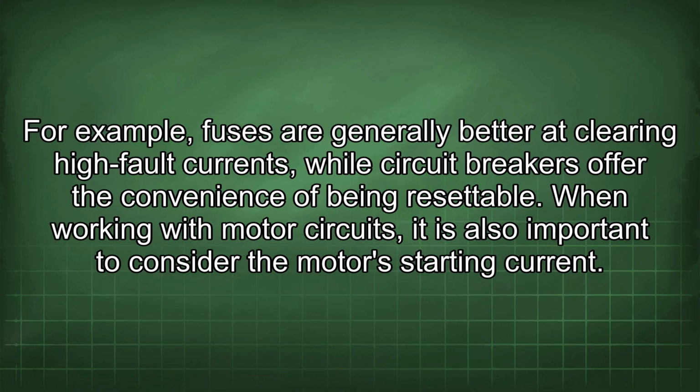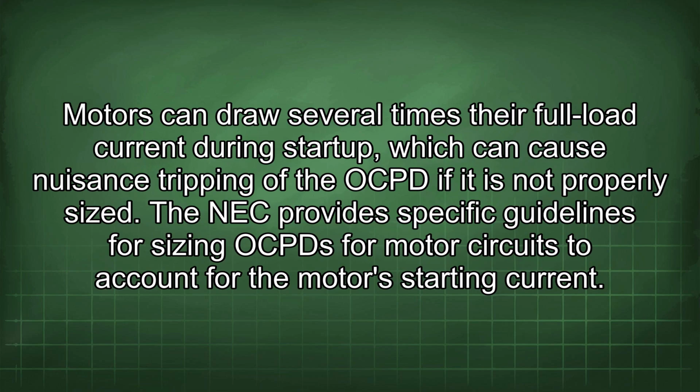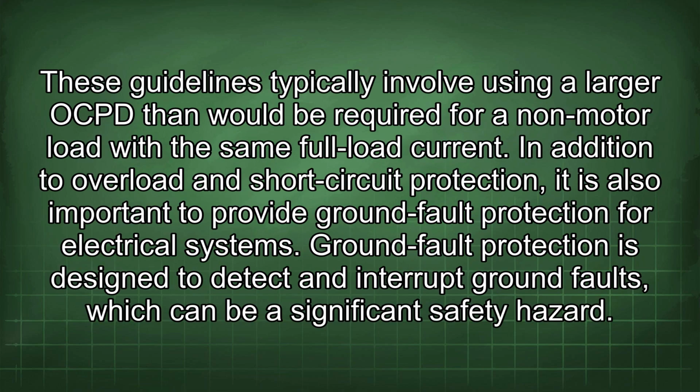For example, fuses are generally better at clearing high fault currents, while circuit breakers offer the convenience of being resettable. When working with motor circuits, it is also important to consider the motor's starting current. Motors can draw several times their full load current during startup, which can cause nuisance tripping of the OCPD if it is not properly sized. The NEC provides specific guidelines for sizing OCPDs for motor circuits to account for the motor's starting current.